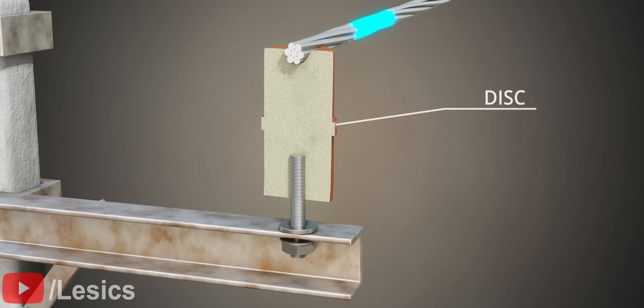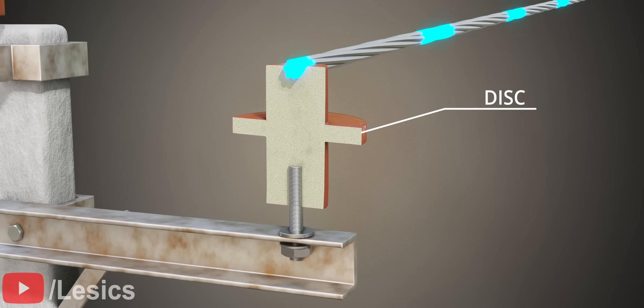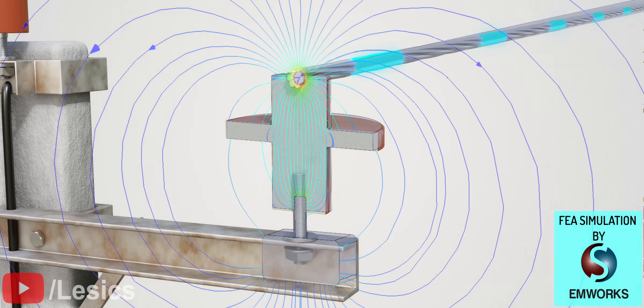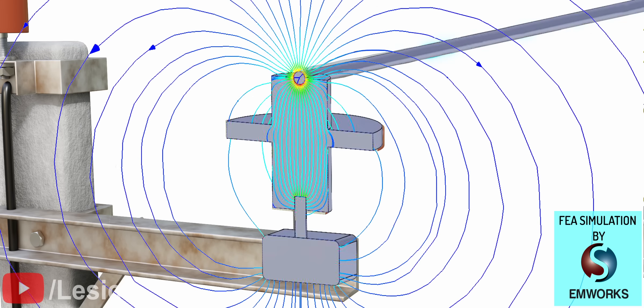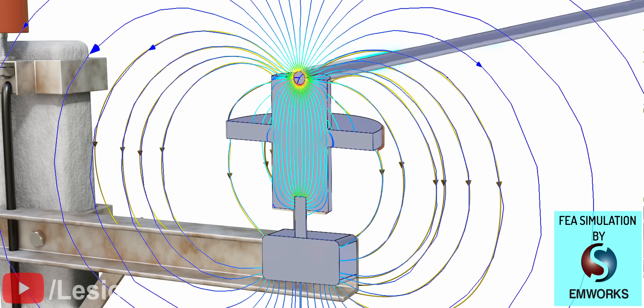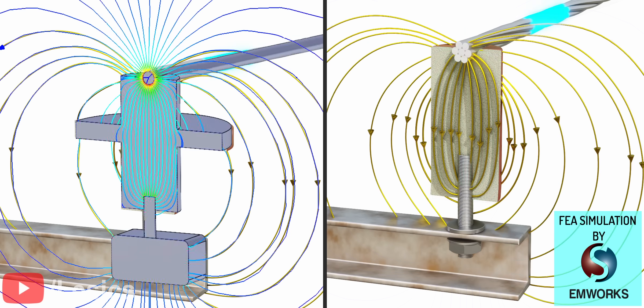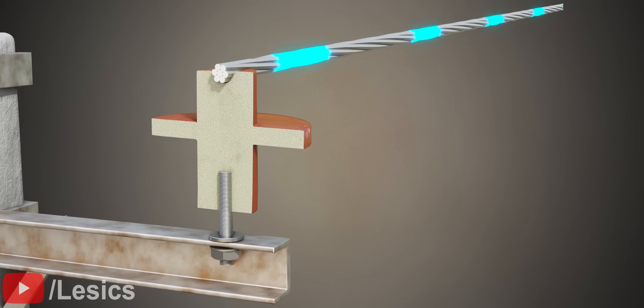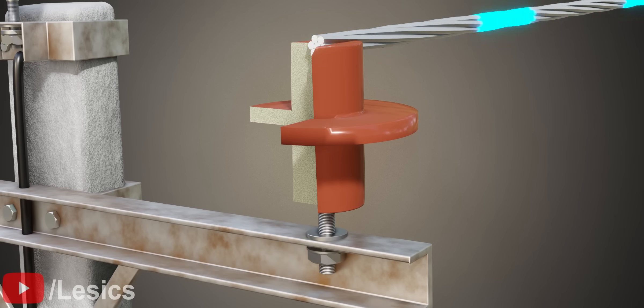We can solve this issue with the addition of a simple disk. This FEA result from EMWorks clearly shows what happens to the electric field lines when a disk is present. You can see that the addition of the disk has reduced the number of electric field lines in the air significantly even though the electric field intensity is the same.